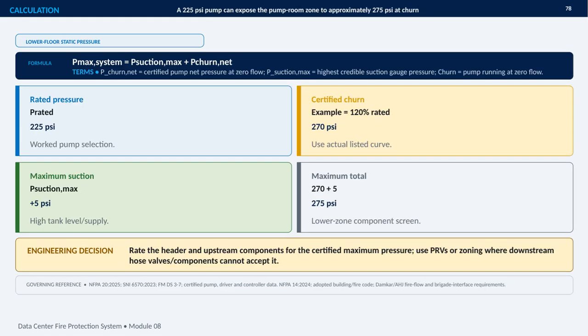This slide shows how to determine the maximum static pressure a lower floor fire protection zone may experience when the pump is running at churn or zero flow. The key relationship is straightforward. Maximum system pressure equals the highest credible suction pressure, plus the pump's certified net churn pressure. The certified pump curve, not simply the rated pressure, governs the calculation.